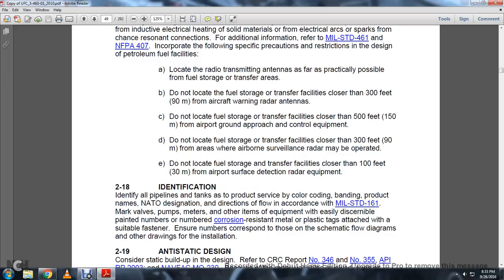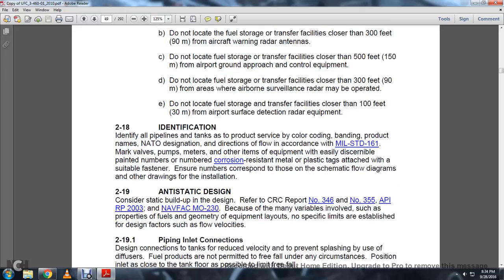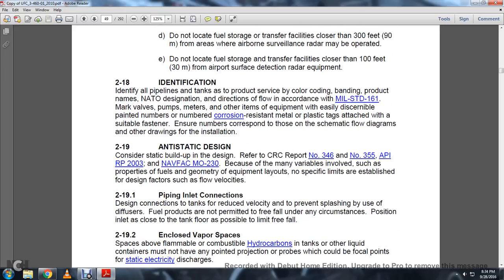2.18 Identification of all pipelines, tanks, and also production surfaces: provide color banding of the product, the name, the NATO designation, and direction of flow in accordance with Military Standard 161. Mark valves, pumps, meters, and other equipment items with easily discernible paint numbers and numbered corrosion-resistant metal and plastic tags attached with a suitable fastener. Ensure the numbers correspond to the schematic flow diagrams and the drawings for the installation.